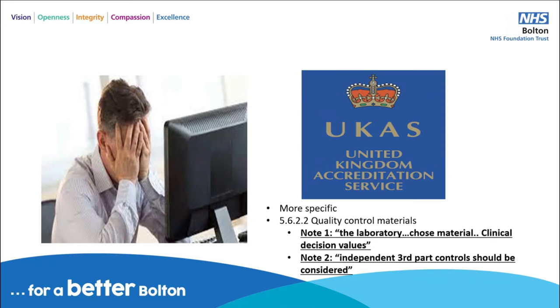And a lot of the wording in UKAS feels like it gives you the option, but we're all aware that there's not necessarily an option to put these standards and controls in place. And one of the key notes that we identified was around the quality control material, which says laboratories should choose material that reflects clinical values and clinical decisions, and that in theory they should implement third party controls. Now, when it says should, it doesn't necessarily mean that. It means that where there's a control available, it should be implemented.